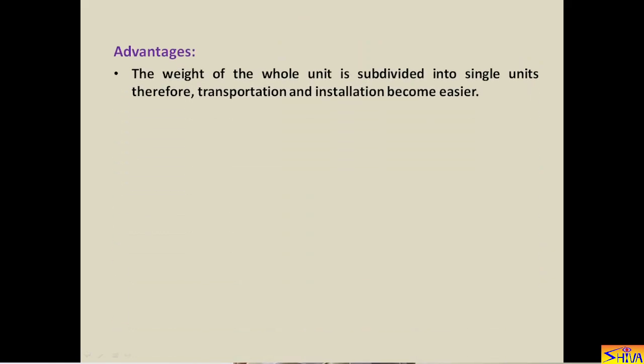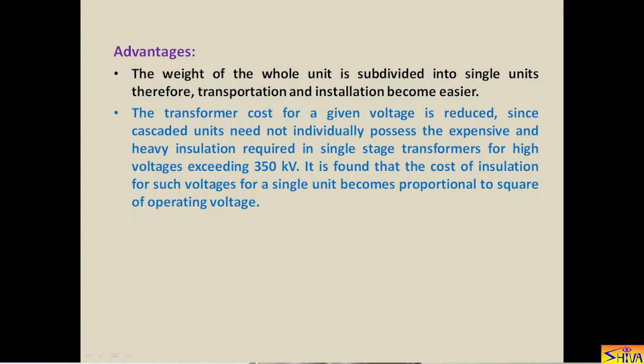Now let us see the advantages. The weight of the whole unit is subdivided into single units, therefore transportation and installation become easier. The transformer cost for a given voltage is reduced, since cascaded units need not individually possess the expensive and heavy insulation required in a single-stage transformer for high voltages exceeding 350 kV.